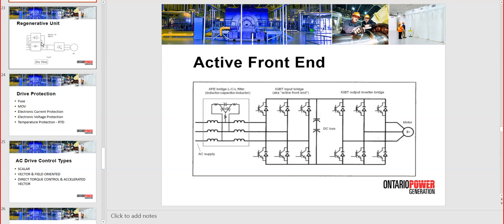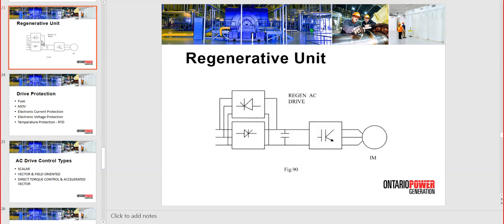So this is an IGBT type drive and is available up to 250 kilowatts. If you need something more powerful, so higher power than that, then you will need to go for the full Regen Drive, the older technology that is available out there. You are gonna need an extra box: you will have the inverter with IGBTs, but the rectifier will be thyristor type, and the reverse box will be attached as a full regen. So whenever the DC voltage goes up because the motor becomes a generator, then the reverse thyristor starts opening and, synchronized to 60 Hertz, will deliver power to the supply grid, except when the supply grid doesn't accept the power. There are exceptions. That's why you have other types of braking. So even if you buy active front end or full Regen Drive, you should have the other dynamic braking installed on the drive.